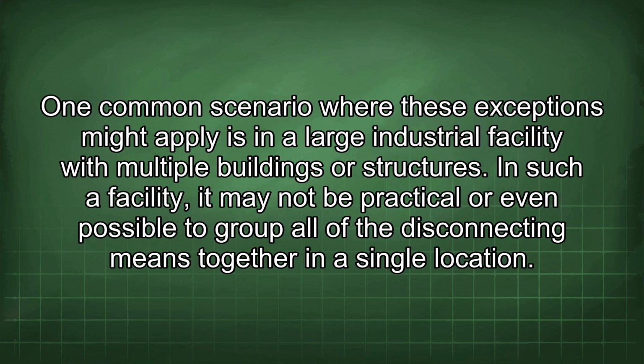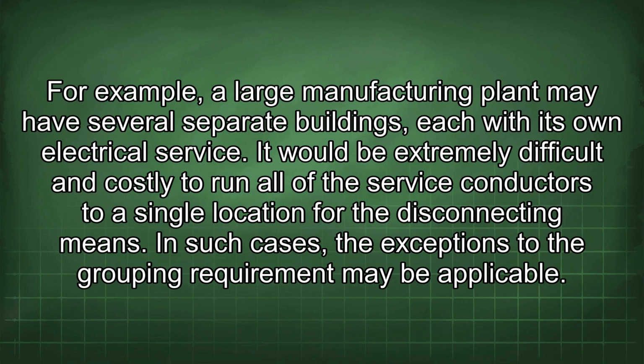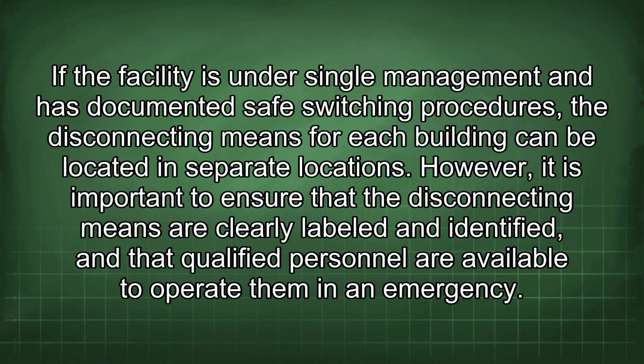One common scenario where these exceptions might apply is in a large industrial facility with multiple buildings or structures. In such a facility, it may not be practical or even possible to group all of the disconnecting means together in a single location. For example, a large manufacturing plant may have several separate buildings, each with its own electrical service. It would be extremely difficult and costly to run all of the service conductors to a single location for the disconnecting means. In such cases, the exceptions to the grouping requirement may be applicable. If the facility is under single management and has documented safe switching procedures, the disconnecting means for each building can be located in separate locations. However, it is important to ensure that the disconnecting means are clearly labeled and identified, and that qualified personnel are available to operate them in an emergency.